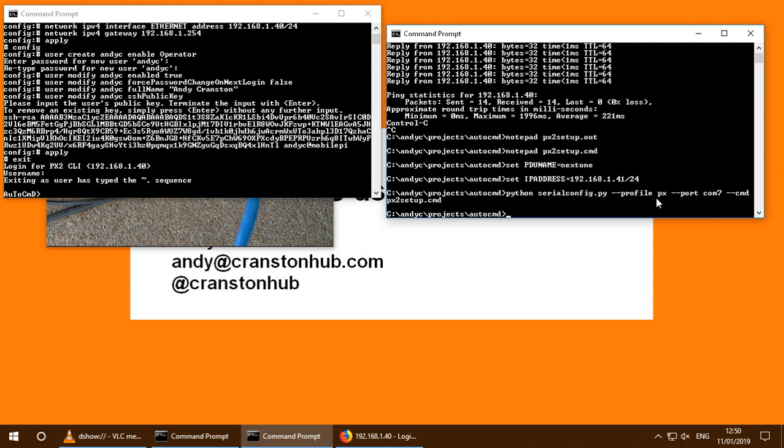So this would be very useful, for example, if you're deploying a lot of Raritan PDUs out on site, say, so you take your laptop along, and as each one gets unpacked and powered up, you can attach your laptop and run the configuration through and assign a unique IP address to each one as you install it in each cabinet as you go around. Or you could pre-configure everything at your office in your deployment lab, then pack everything up, take it on site, install everything into the correct cabinets, attach straight onto the customer network, and hey presto, you're up and running. Everything's got a secure password, fixed IP, and you'll look fantastic, and you'll be on site for less time.